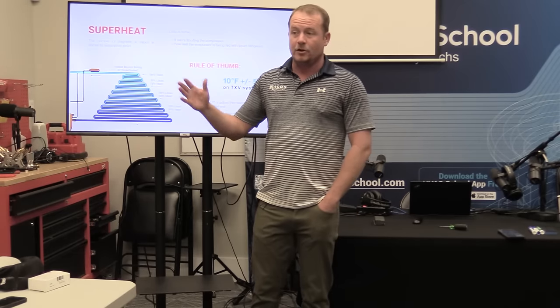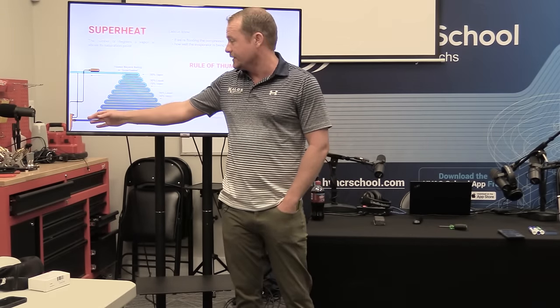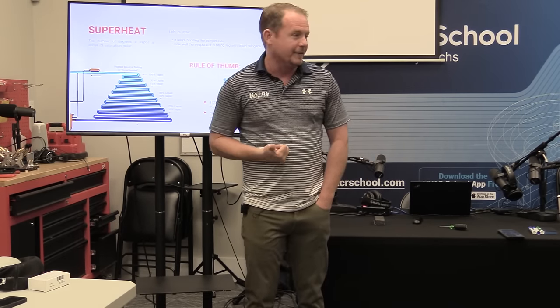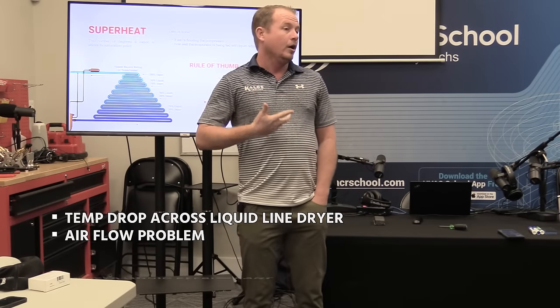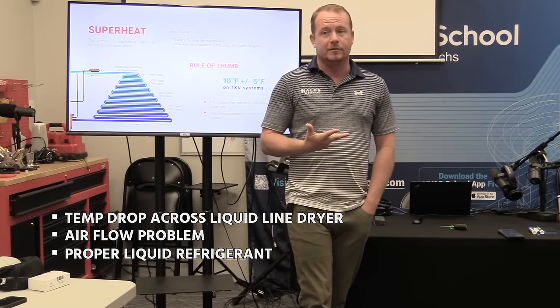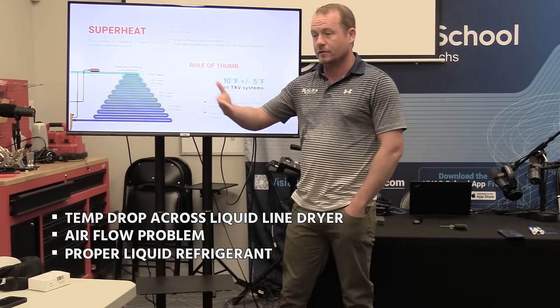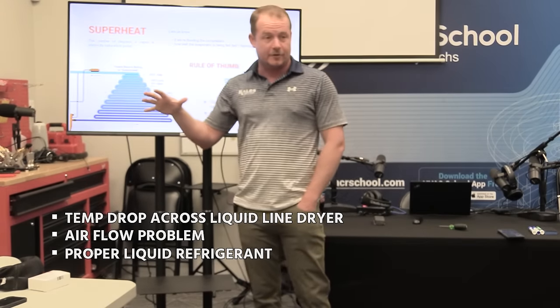We watch our superheat on most of the systems we work on just to make sure the metering device is doing what it's supposed to do. If our superheat drops too low, that's an indication the valve is overfeeding. If our superheat is too high, that's an indication the valve is underfeeding — if everything else is how it's supposed to be. And that's the key thing.